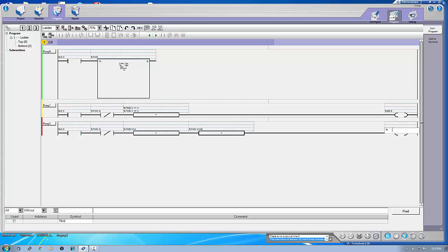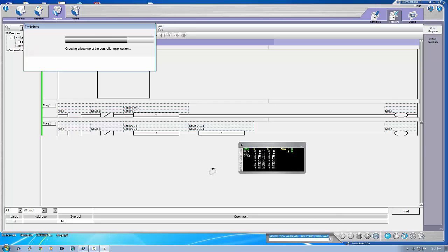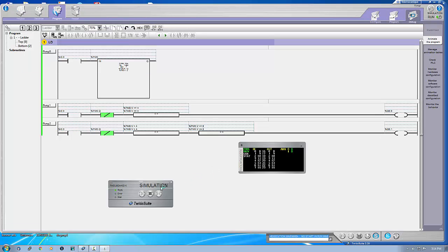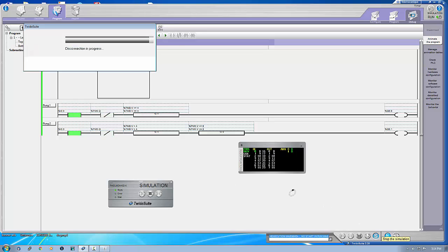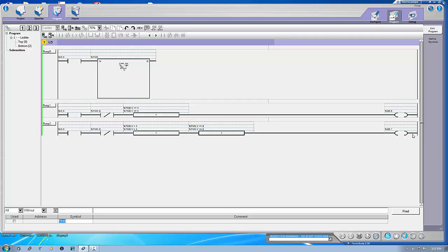Let's put an output — Q:0.1. Let's try this — it's clear, no errors. Now let's put it in run mode. For the first four seconds the first output is on. For the next four seconds the second output is on. As soon as it becomes eight seconds it turns off. But if you don't put another compare block it would stay on till 12 seconds.